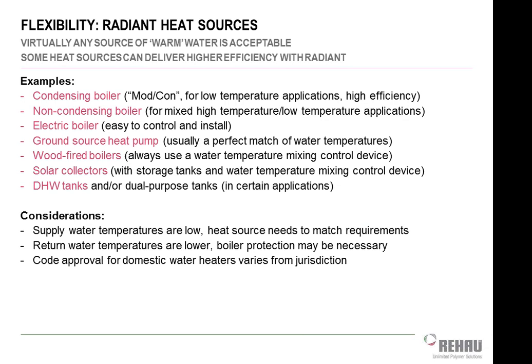Solar panels have become popular lately to use for both domestic water as well as radiant heating systems, and you can also tie them into other renewable-like sources such as a wood-fired boiler or a corn-fed boiler or something like that. Just keep in mind that the water temperature needs to be very low compared to a traditional system. So if you have a hot heating device like a full cast iron boiler or a wood-fired boiler, you'll have to have mixing valves.